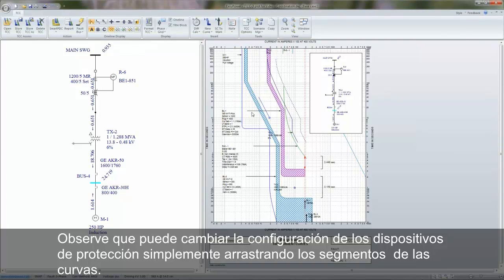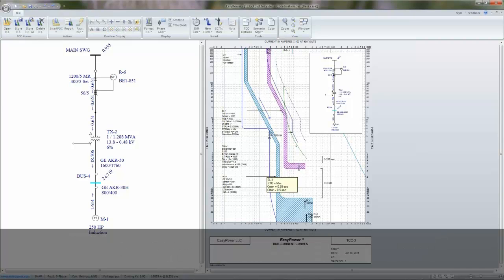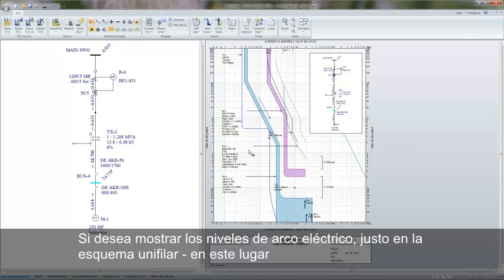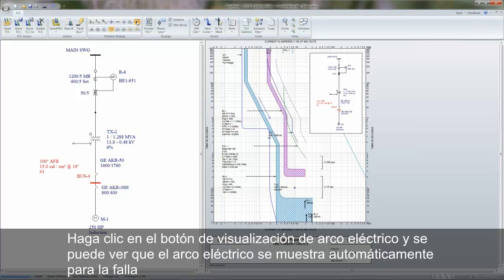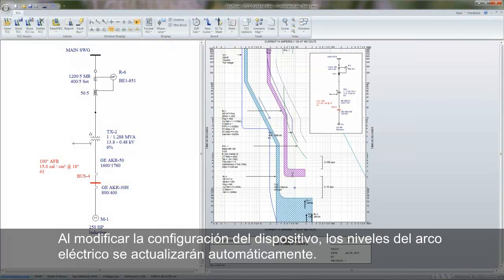Notice that you can change settings on protective devices by simply dragging the portions of the curves. If you want to show arc flash levels right on the one line, at this location, click on the arc flash display button, and you can see that the arc flash is displayed automatically for the fault. As you modify the device settings, the arc flash levels will automatically update as well.